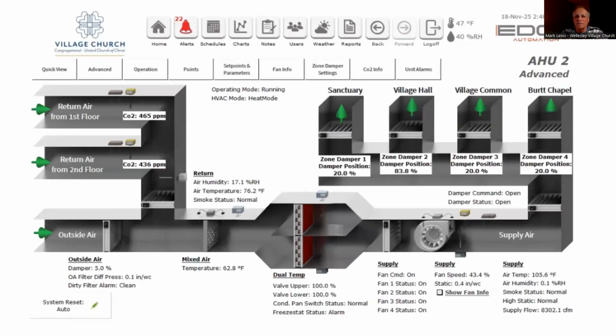Integrated design. This is a modern building management system. For those of you that haven't seen one, this is the air side of it. It shows on the left the return air coming from our building mixing with outside air, so it's fresh. Then in the middle center, you'll see the red heating tubes. This is an actual screenshot in the heating mode, and if you follow it up around, you can see zone damper number 2 is at 83% because that space is calling for heat. We can monitor this, graph it, get alarms on it. We learned so much more about running our building than we did with our old system. In fact, that's one of the lessons learned. I'll tell you about it at the end. Next slide.